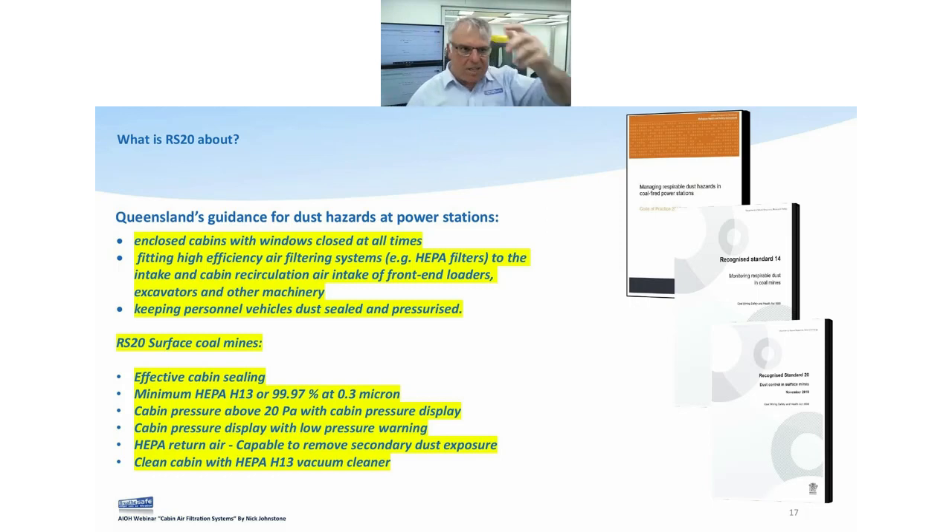Looking at the standards: guidance for power stations says enclosed cabins with windows closed at all times, high efficiency air filtration — HEPA filters on intake and recirculation, both fresh air and recirculation. Keeping personnel vehicles dust-sealed and pressurized — sealing and pressurizing always run hand in hand. Then we've got RS20, our latest standard. Effective cabin sealing is always going to be number one — without it, even with no system on at all, you'll actually dramatically increase respirable dust inside.